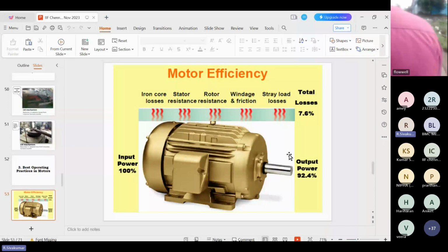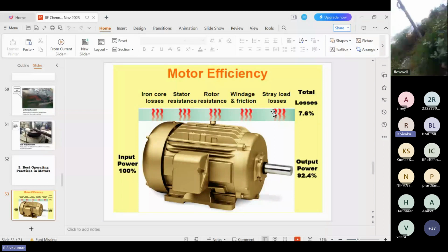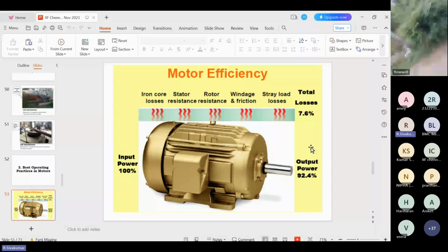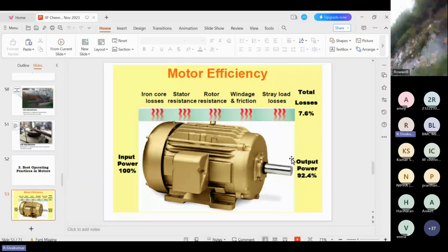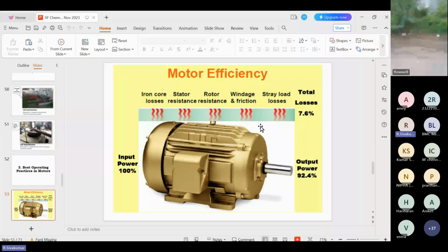So what are the various losses available? Basically, the motor consists of a stator and a rotor. Inside there are iron and core losses, stator resistance losses, rotor losses, windage and friction losses of almost 1.5 to 1.8%, and stray load losses. All losses put together, the total losses are somewhere around 7.6% for a new motor. So maybe this category is the IE2 or IE3 motor, for any make, Siemens or ABB or Crompton Greaves, any make. The IE2 or IE3 standard says 92.4% is the efficiency.